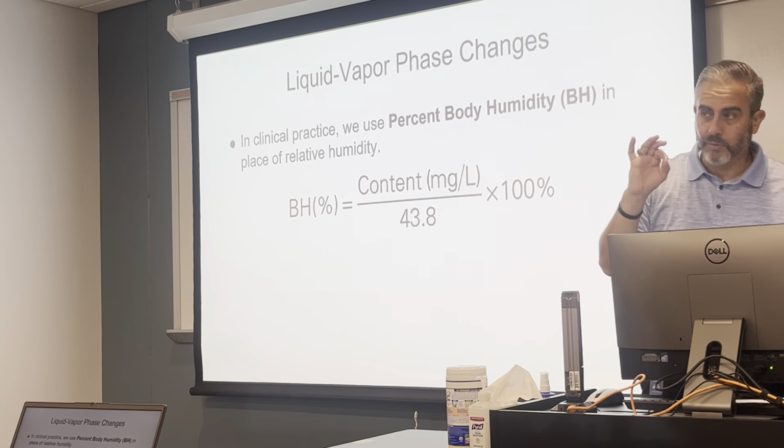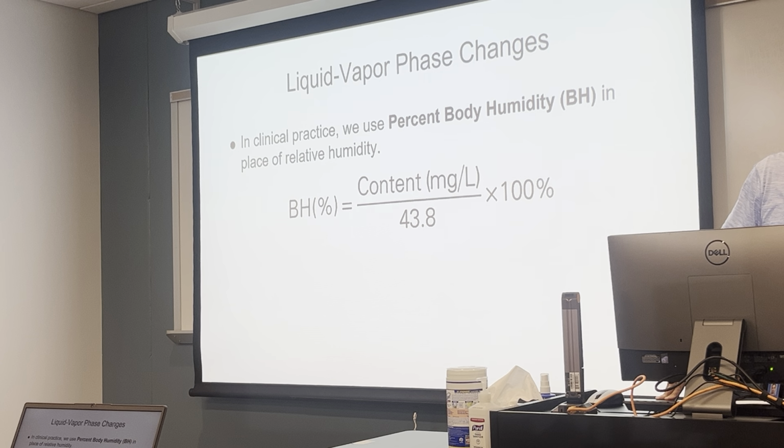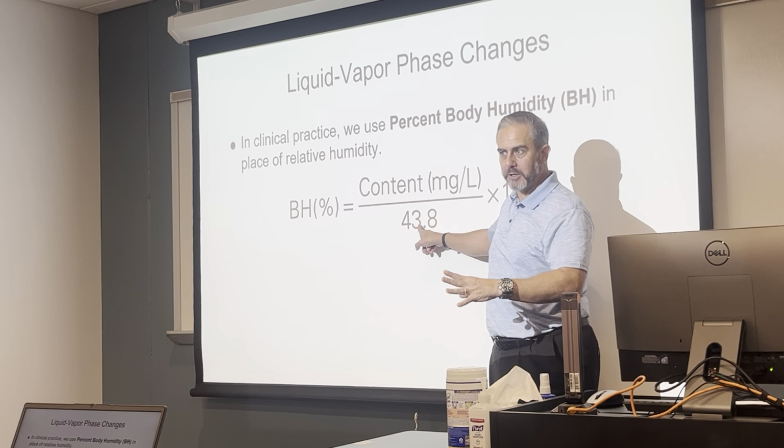So you would give us a formula like that, just omitting the body humidity, and expect us to know that to calculate the formula out? Or is that what you're saying? Body humidity. Body humidity. So, yes, I will tell you the humidifier we selected is carrying whatever the number is going to be. This amount. The content of this humidifier is, and I'll use the previous example, 22. Okay? What is its body humidity? Now, I didn't give you the saturated capacity. You have to remember, because we're talking body humidity, what the body requires is 44. So that's its saturated capacity all the time.